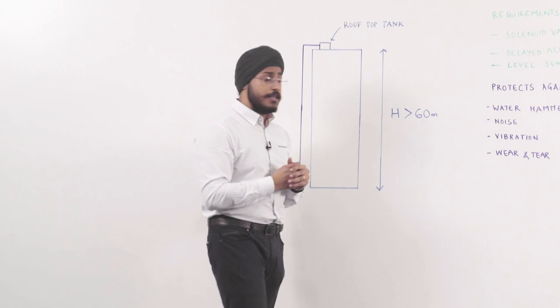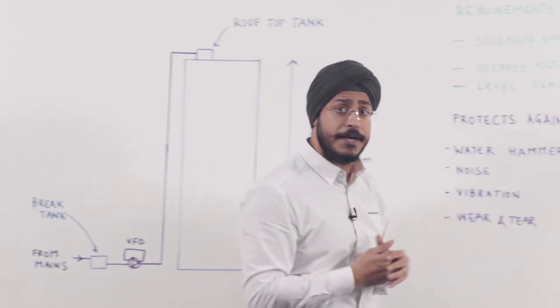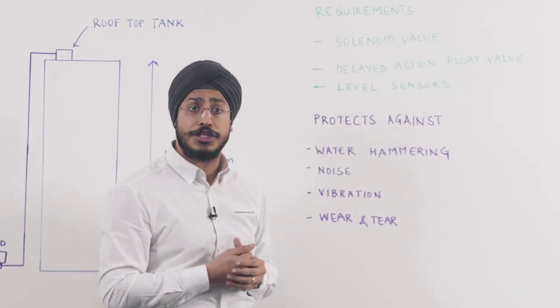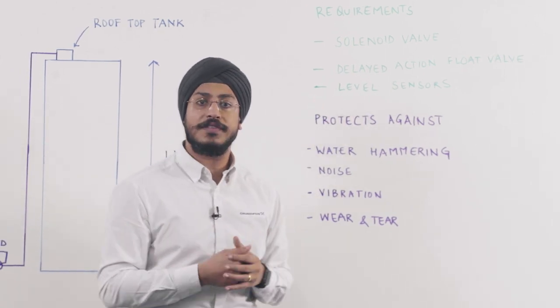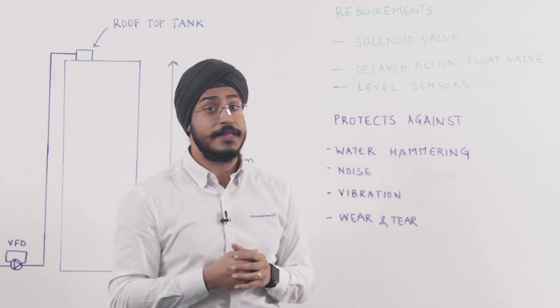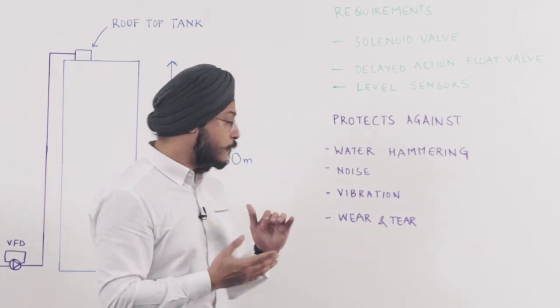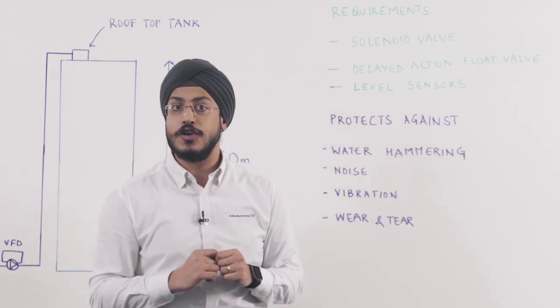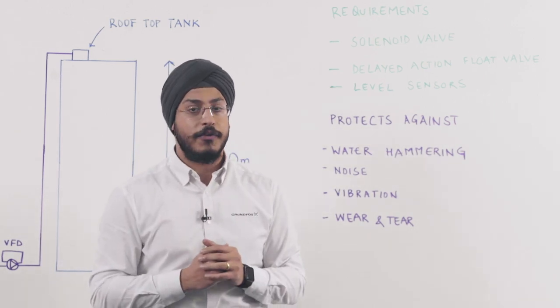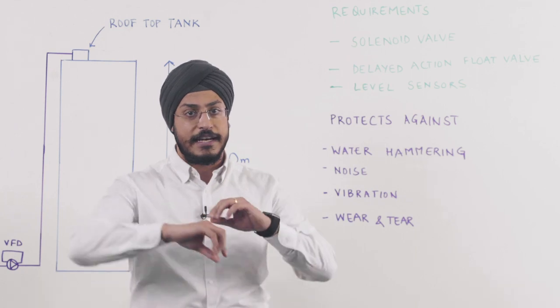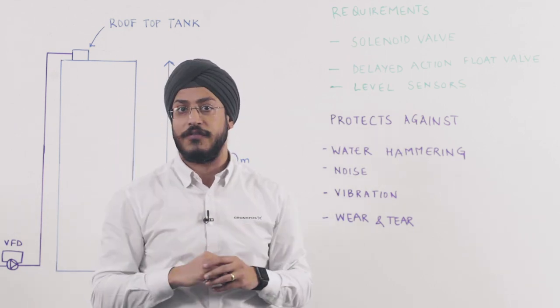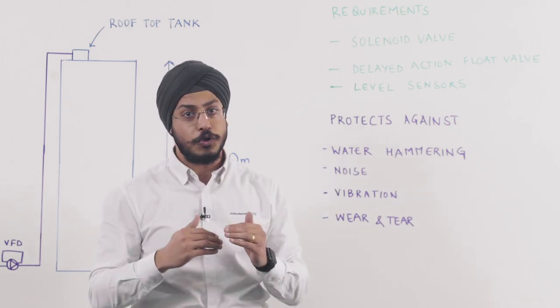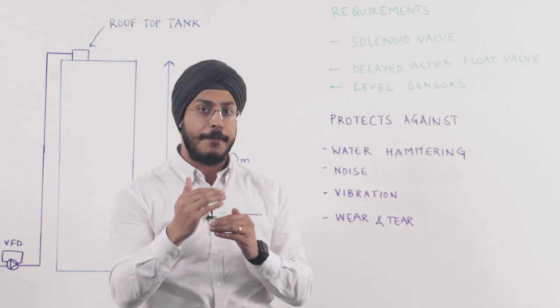In this case, in the rooftop tank, there are some additional requirements. We need to use solenoid valves or delayed action float valves. These valves help create a pressure drop in this line because in this case, the pressure boosting system will work on a pressure control, not on a level control. Which means that when the line starts to empty because of the opening of this valve, the pressure in the line will drop, indicating the pump to increase its speed and ramp up slowly.